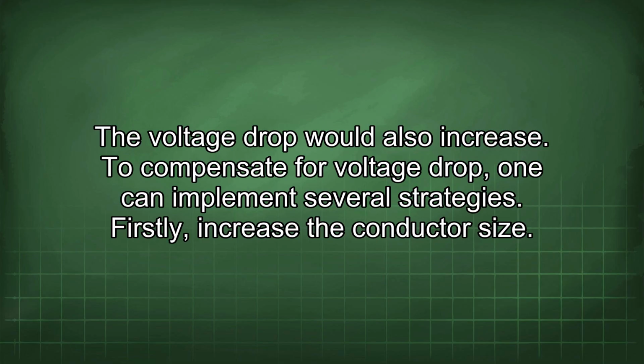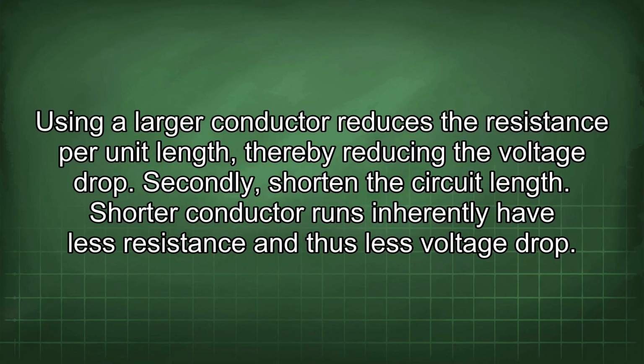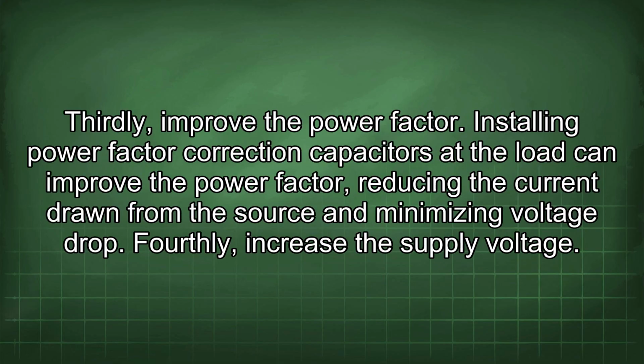To compensate for voltage drop, one can implement several strategies. Firstly, increase the conductor size. Using a larger conductor reduces the resistance per unit length, thereby reducing the voltage drop. Secondly, shorten the circuit length. Shorter conductor runs inherently have less resistance and thus less voltage drop. Thirdly, improve the power factor.